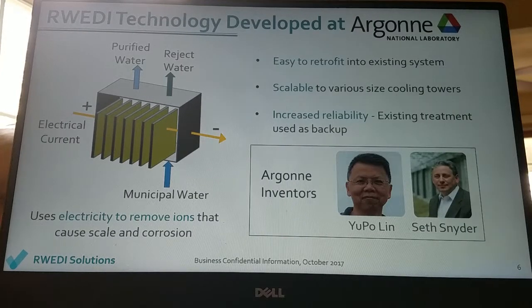The Ready Water system is a fundamentally improved electrodeionization process, which improves the water quality unlike our competitive processes. The Ready Water technology is built from commercially available components and Argonne's patented resin wafer design to enhance the system performance and flexibility. The inventors Yupo Lin and Seth Snyder have over 25 years' experience in water technology development. If you stack the resin wafers that they've invented into a water treatment device, you can use electricity to pull the scale-forming ions into a reject water stream, sending purified water to the cooling tower. Our device is easy to retrofit into existing infrastructure, has a modular design to scale to various size cooling towers, and we maintain the existing chemical treatment system to increase reliability.